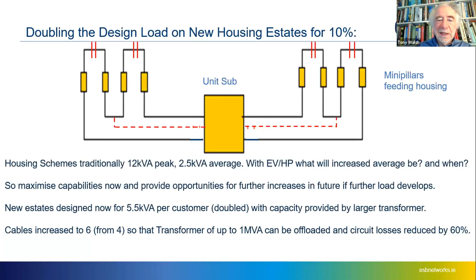In urban estates, on the outskirts of urban areas, they can still be fed from pole-mounted transformers. These pole-mounted transformers have a maximum size of 200 kVA. Above that, we've no solution, so we can either put in a second pole mount or a unit sub. Problem is, where do you find a place to put in a pole, or a unit sub, in a mature development? Very difficult.